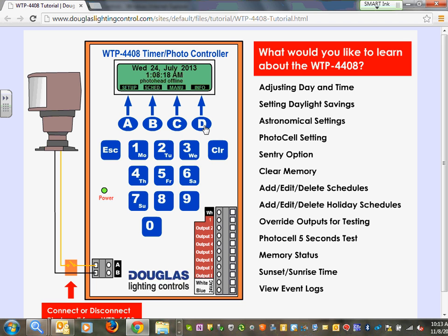We have a series of gateways that we get. We have a gateway that lets us talk to anybody's building management system. We just have to know whose it is, right? So we convert a Johnson Controls Metasys building management system. We put a gateway between it and this that lets them see us downstream, right? Lets them do programming, which we really, really don't like, because quite honestly, they do mess up the lighting. When I have to go back to a building because the lighting control system is messed up, 99.9% of the time it's because the building management guy started trying to change lighting functionality. It's not the same thing.